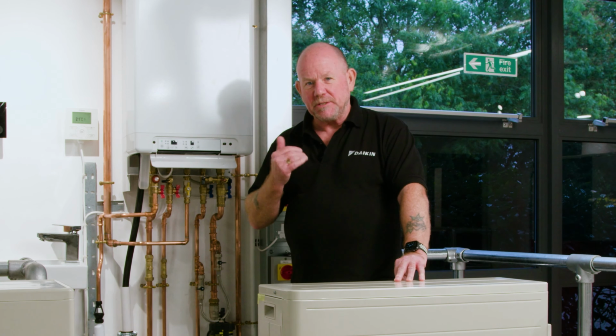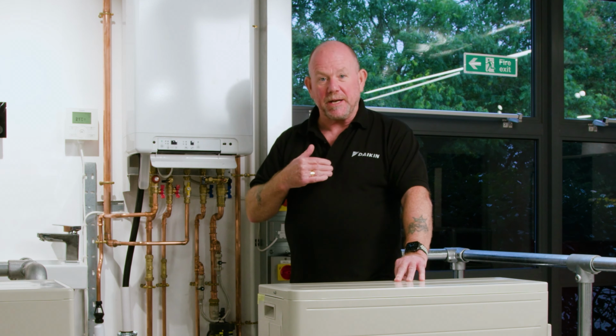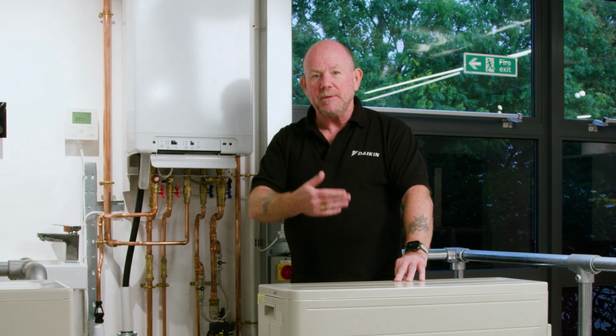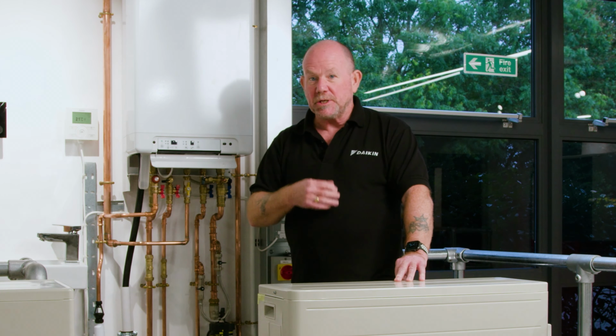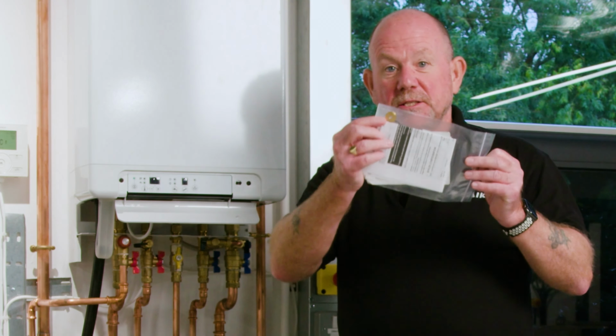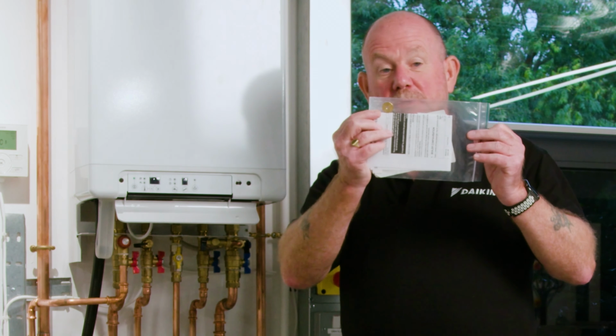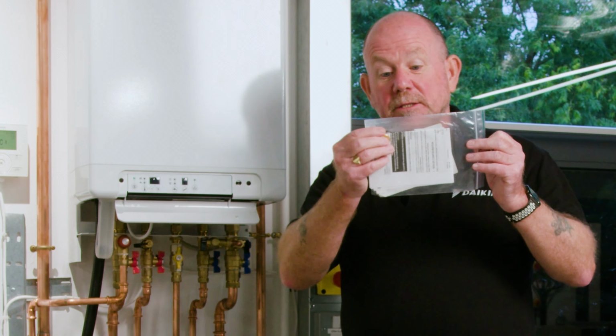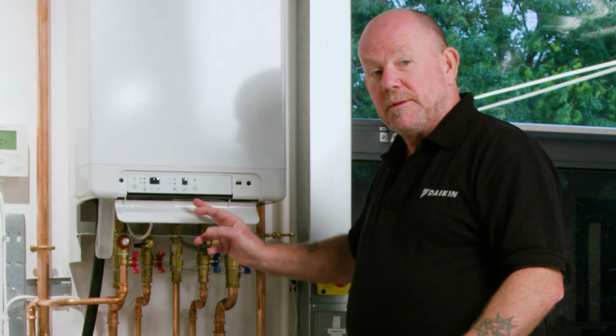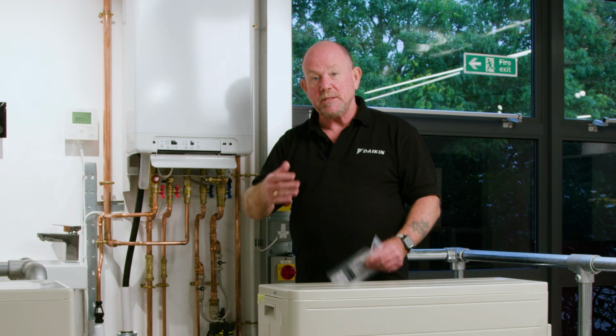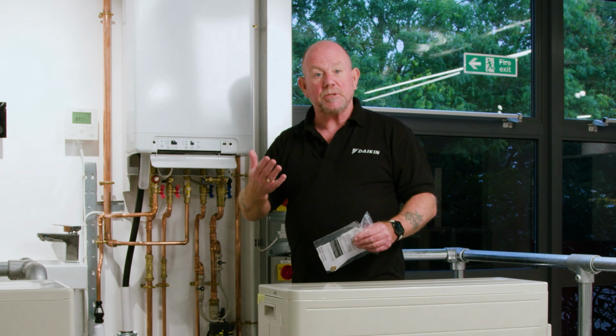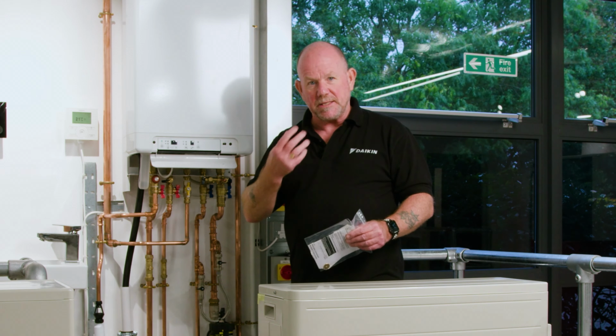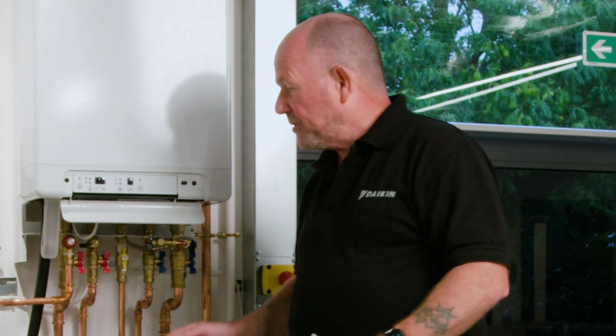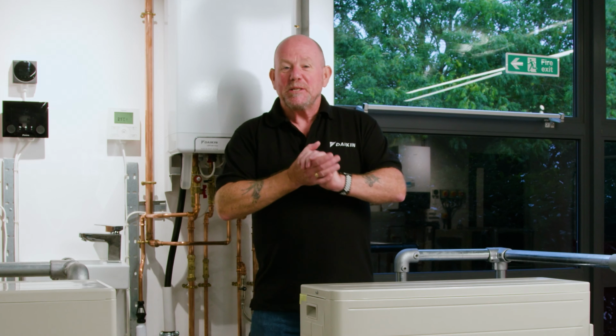One topic we haven't spoken about is just how easy the boiler is to convert from natural gas to LPG. The boiler will be delivered to you as a natural gas boiler. To convert to LPG, you'll need a conversion kit. The conversion kit contains simply a restrictor ring. There will be a natural gas restrictor ring on top of the gas valve in the boiler as delivered. Change the ring for the one in the conversion kit. Then there are 2 parameters to change within the diagnostics of the boiler. Once those parameters are changed and the restrictor ring is changed, it's simply combustion analysis to make sure the performance of the boiler is as expected. Once complete, the most important thing to remember to do is to hide those buttons away from the end user again.